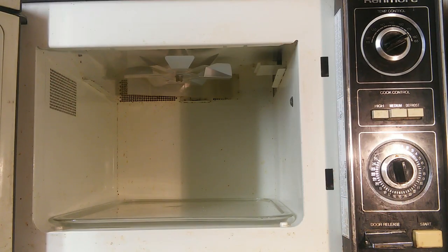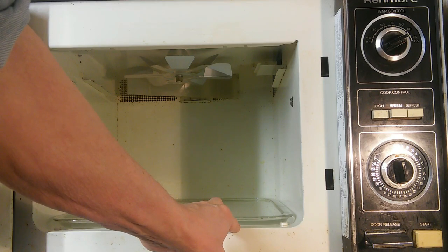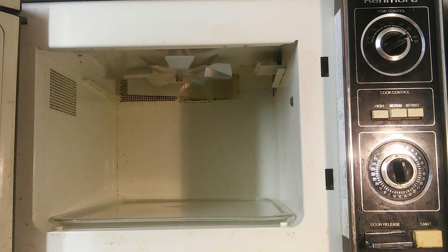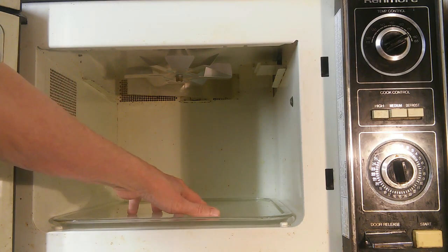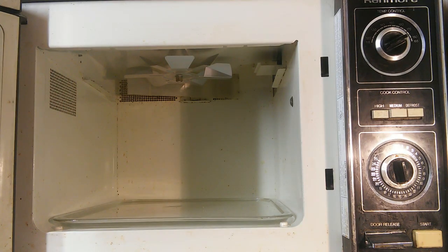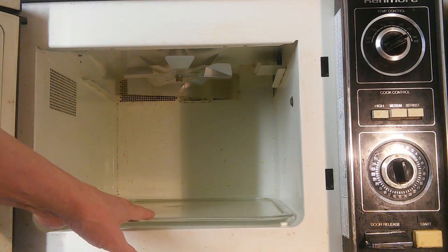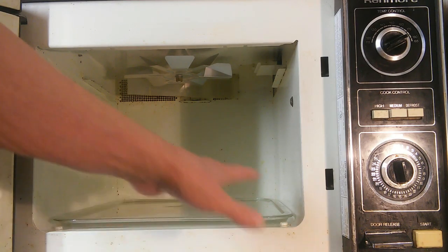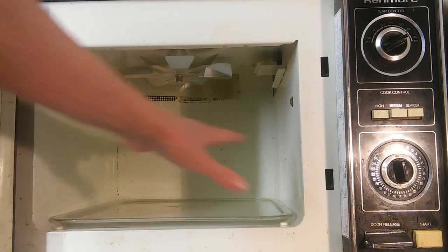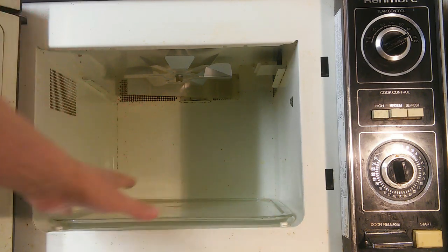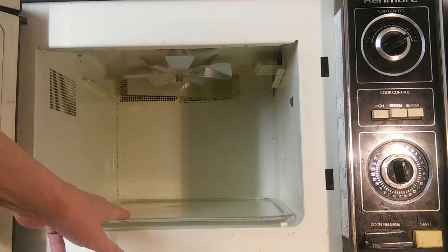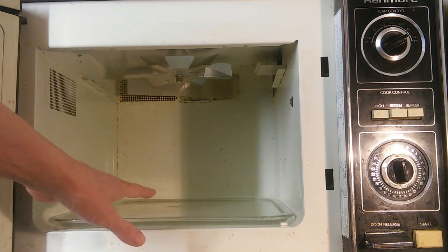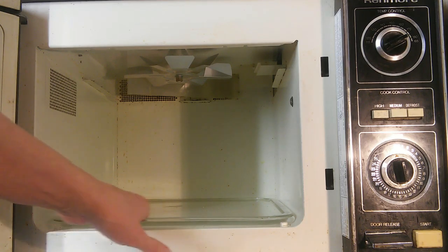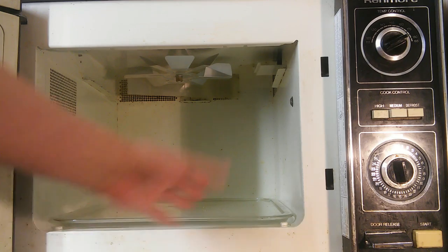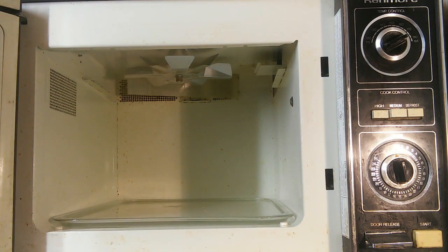Back to the problem we're having: the cooling fan turns on after a long delay, so for the first minute or so you get the standing wave pattern, and food will burn on one side and be uncooked on another. It takes about a minute or so for that fan to come on, depending on the ambient temperature - if the room is warmer it comes on quicker, but if it's cool it can take a really long time. The ambient temperature in my house in winter is probably mid to upper 60s, and it can take a really long time for this thing to start.